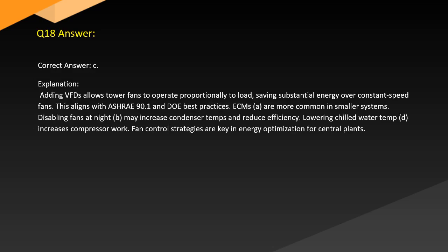Answer. Correct answer: C. Explanation. Adding VFDs allows tower fans to operate proportionally to load, saving substantial energy over constant speed fans. This aligns with ASHRAE 90.1 and DOE best practices. ECMs are more common in smaller systems. Disabling fans at night may increase condenser temps and reduce efficiency. Lowering chilled water temp increases compressor work. Fan control strategies are key in energy optimization for central plants.